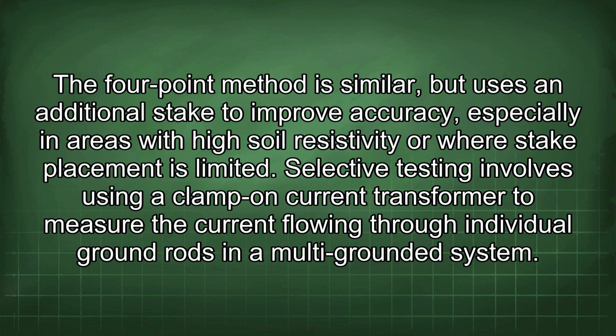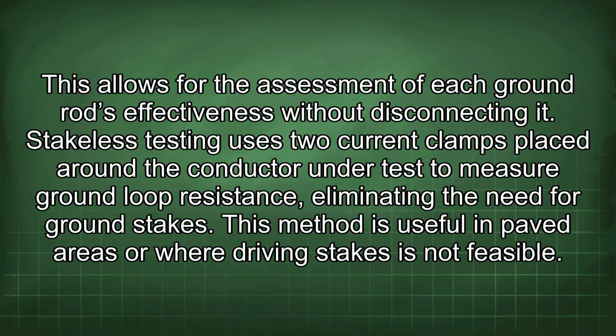The 4-point method is similar, but uses an additional stake to improve accuracy, especially in areas with high soil resistivity or where stake placement is limited. Selective testing involves using a clamp on current transformer to measure the current flowing through individual ground rods in a multi-grounded system. This allows for the assessment of each ground rod's effectiveness without disconnecting it. Stakeless testing uses 2 current clamps placed around the conductor under test to measure ground loop resistance, eliminating the need for ground stakes. This method is useful in paved areas or where driving stakes is not feasible.